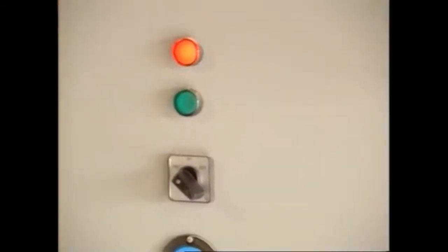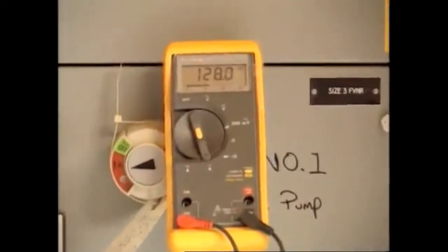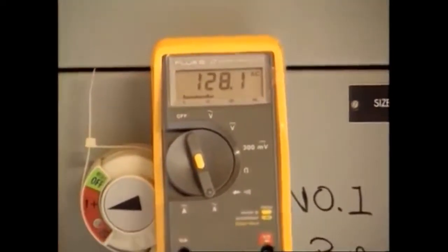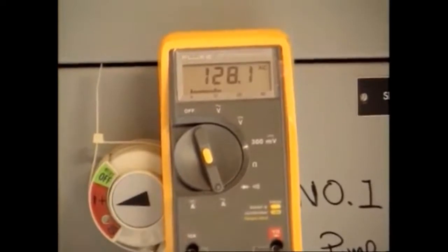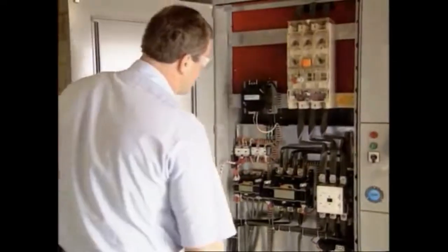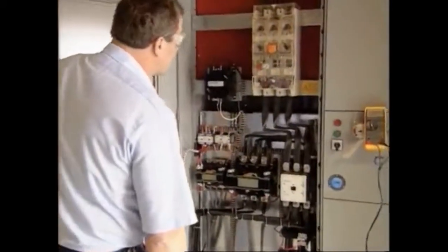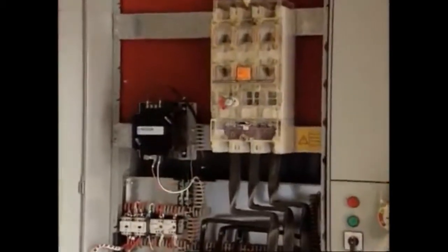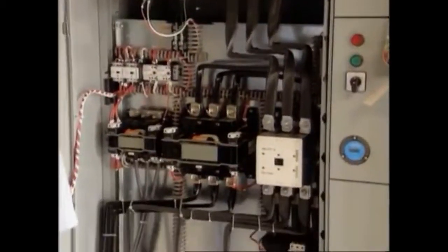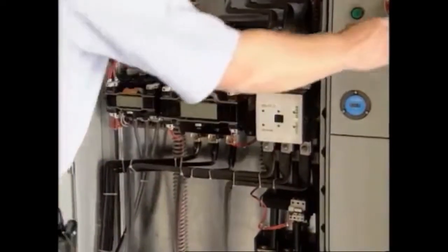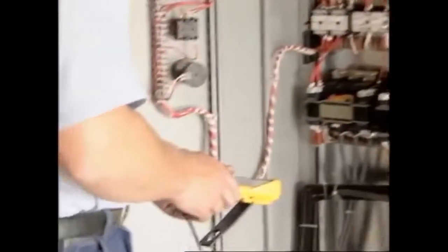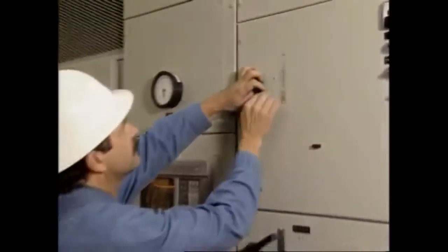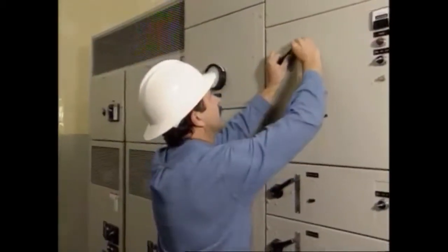Motor overloading is the operation of the motor in a way that causes it to draw current in excess of what's recommended by the manufacturer and shown on the motor nameplate. The heat generated by continuous operation above its design rating is extremely damaging to the insulation. If the motor is operating in an overloaded condition, you must determine the cause of the overload. The first step in the solution may be to avoid continuous operation. However, continuous operation may be preferable as opposed to starting and stopping when the motor is undersized.